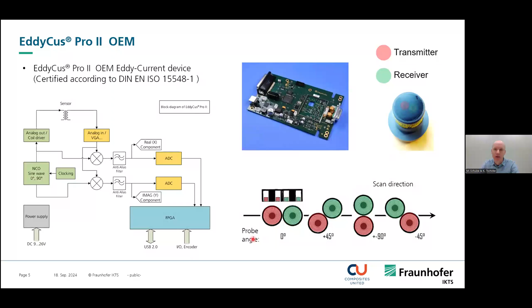Typically, we use anisotropic probes, so we have a transmitting and a receiving coil. By rotating the probe angle, we can focus into different layers and orientations of the sample, and can also optimize the sensitivity of our system.